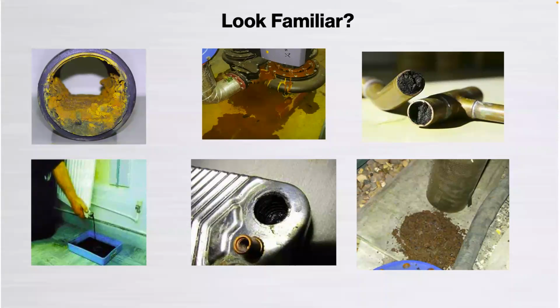I've even seen hard hats, steel toe cap boots and a pair of overalls come out of a condenser strainer once on a brand new system. Once the velocities were pushed up, we had a huge differential pressure across the strainer, and that was removed. So it's really important that we've bypassed everything.